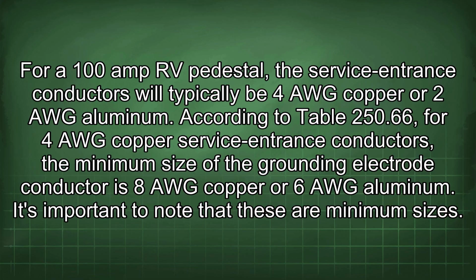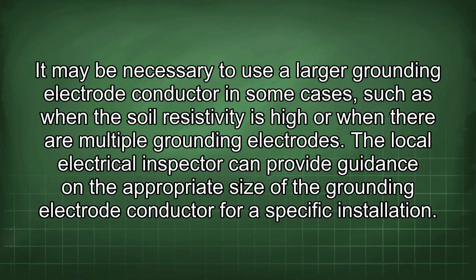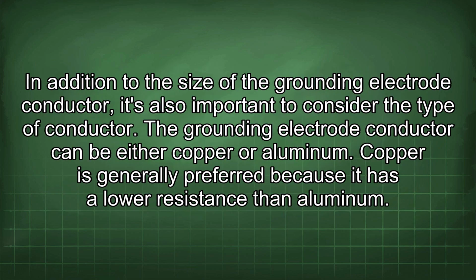According to Table 250.66, for 4 AWG copper service entrance conductors, the minimum size of the grounding electrode conductor is 8 AWG copper or 6 AWG aluminum. It's important to note that these are minimum sizes. It may be necessary to use a larger grounding electrode conductor in some cases, such as when the soil resistivity is high or when there are multiple grounding electrodes. The local electrical inspector can provide guidance on the appropriate size of the grounding electrode conductor for a specific installation.